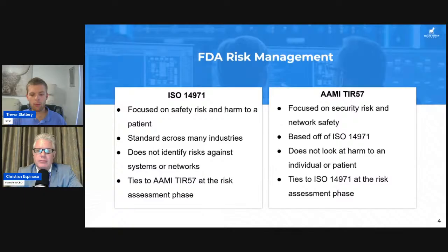And one thing that we really like to do is talk about how we are getting this intersection between safety and security. During the risk management phase, there's a specific point following an AAMI TIR57 risk management framework where we say, are we doing a cross evaluation for safety risks within the product? Notably, we are not talking about a cross evaluation with business risk. We're not talking about financial risk. So it becomes apparent how security risks in a medical device can introduce a safety problem.